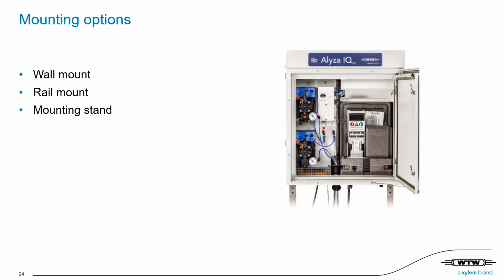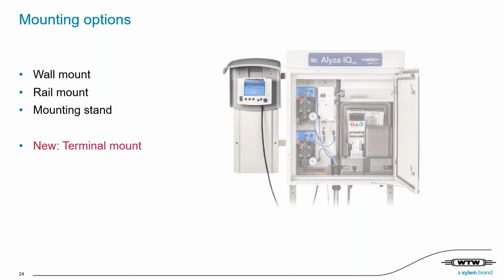So in addition to the filtration, I would like to give you a quick overview on the mounting options of the new analyzer. To fit to all conditions at the measurement site, we provide mounting accessories for the mounting at a wall, a rail, or even use a mounting stand if none of it is available. Here is an additional mounting option for a terminal controller directly at the analyzer. Thanks to this terminal mount, you always have it displayed right next to the unit.